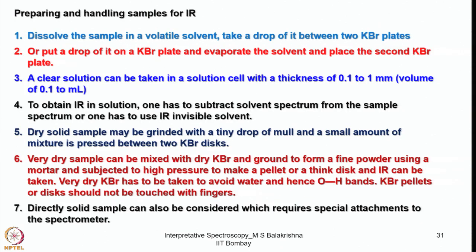Now let us look into how to prepare samples for recording IR spectra. Dissolve the sample in a volatile solvent such as dichloromethane or heptane, take a drop of it between two KBr plates or put a drop on a KBr plate, evaporate the solvent, and place the second KBr plate on top like sandwiching. A neat sample can also be recorded. Alternatively, a clear solution can be taken in a solution cell with a thickness of 0.1 to 1 mm and a volume of about 0.1 ml. To obtain IR in solution, one has to subtract the solvent spectrum from the sample spectrum or use an IR-invisible solvent.